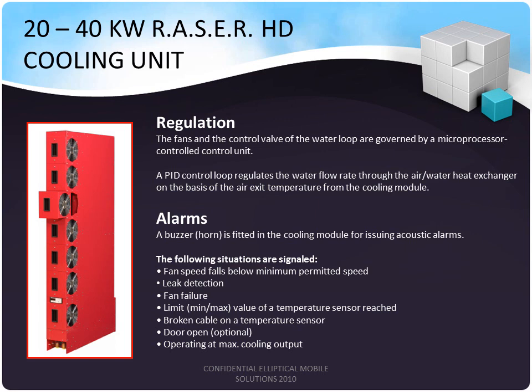The RASER cooling units are highly sophisticated and contain quite a few sensors. They are regulated with microprocessor-controlled units. The PID control loop regulates the water flow through the air and water heat exchanger on the basis of air exit temperature from the cooling module, so they are self-regulating. A buzzer or horn fitted on the cooling unit can issue alarms for fan speed, leak detection, fan failure, temperature limits (minimum or maximum), broken connectivity to any temperature sensors, an open door, or if the unit is operating at maximum cooling temperature.